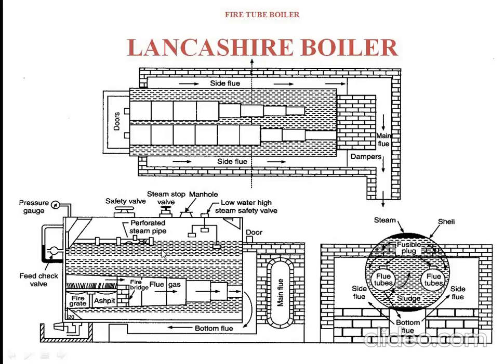Every boiler consists of mountings as well as accessories. Mountings are for safety purposes; accessories are for increasing the efficiency of the boiler. Here you have mountings such as: safety valve, steam stop valve, manhole, low water high steam safety valve, feed check valve, pressure gauge, and blow-off cock. The blow-off cock is used to empty the boiler and to remove dust particles or mud present inside. The pressure gauge reads the pressure of steam generated. The safety valve safeguards the system under high pressure. The steam stop valve allows use of the steam. The manhole allows a person to enter inside for inspection. The low water high steam valve alerts the system when water is low.